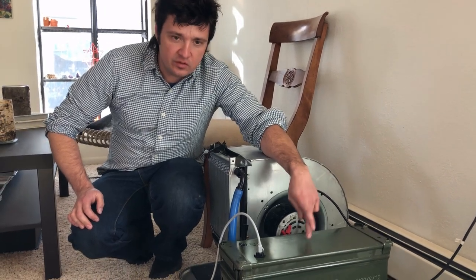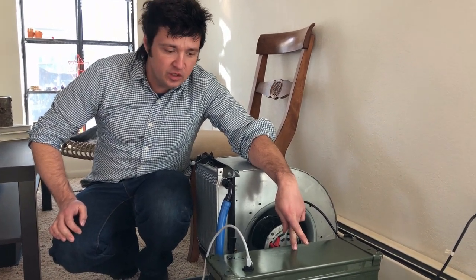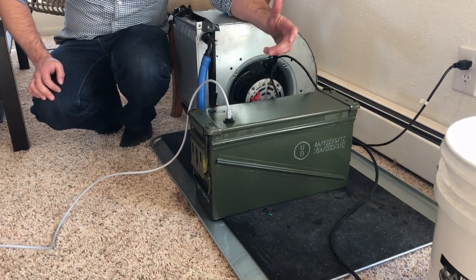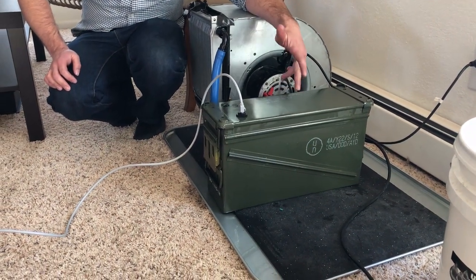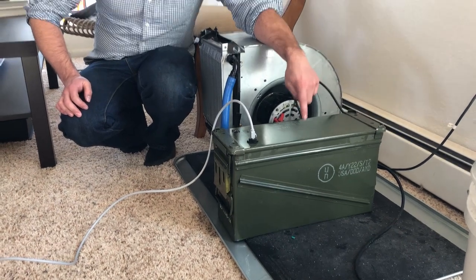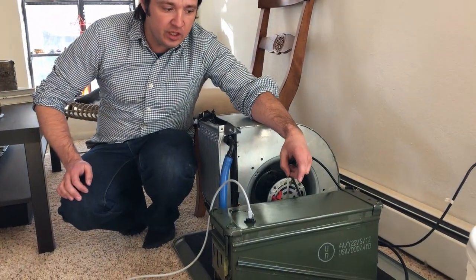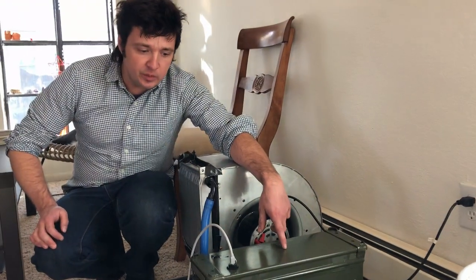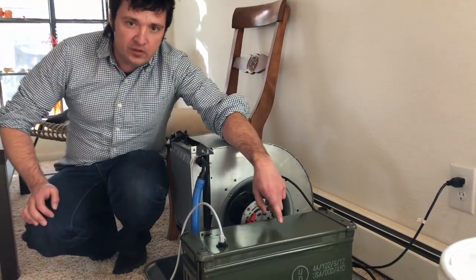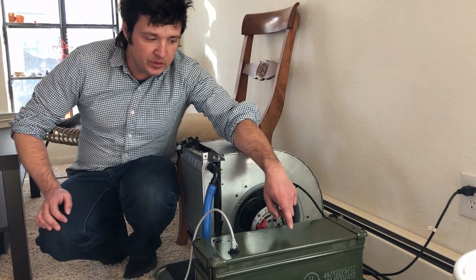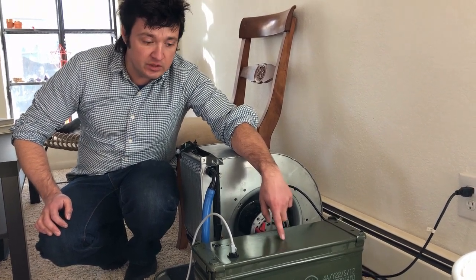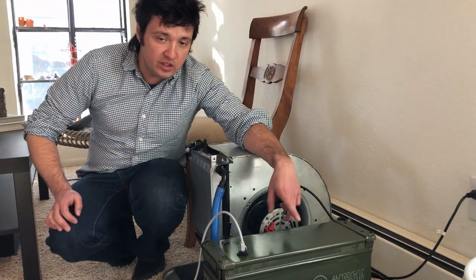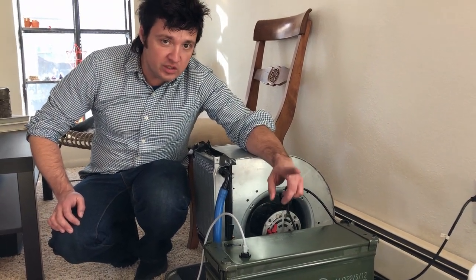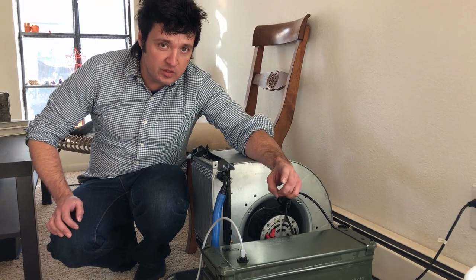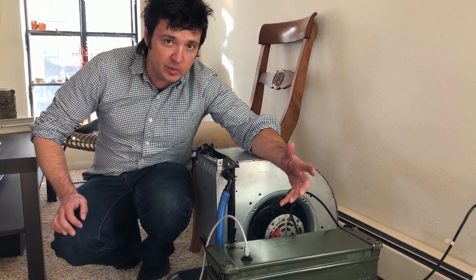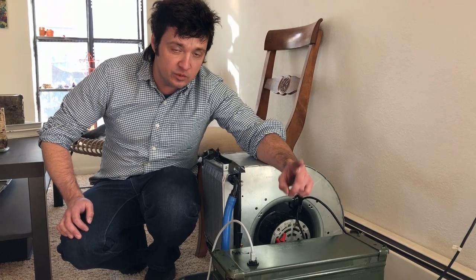When you run this, it's very important that you keep your lid closed to ensure no dust or dirt gets in, but also this oil will pick up water if it's exposed to the air, and it can mist up a little and get on everything. If you use transformer oil, it will smell quite a bit if you don't keep the lid on. If you're outside of the US and you get transformer oil, make sure it doesn't have PCBs, which are compounds that make it more stable, but they're also extremely biotoxic and will make you sick.